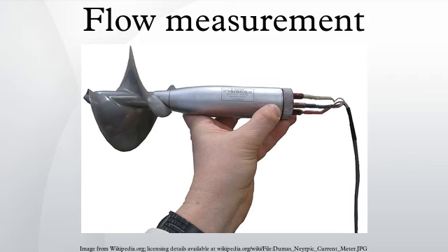Electromagnetic, ultrasonic and Coriolis flow meters. Modern innovations in the measurement of flow rate incorporate electronic devices that can correct for varying pressure and temperature conditions, non-linearities, and for the characteristics of the fluid. Magnetic flow meters, often called mag-meters or electromags, use a magnetic field applied to the metering tube, which results in a potential difference proportional to the flow velocity perpendicular to the flux lines. The potential difference is sensed by electrodes aligned perpendicular to the flow and the applied magnetic field. The physical principle at work is Faraday's law of electromagnetic induction.